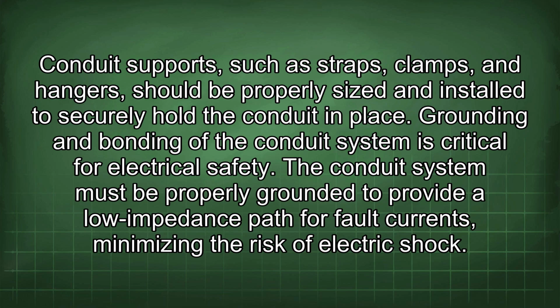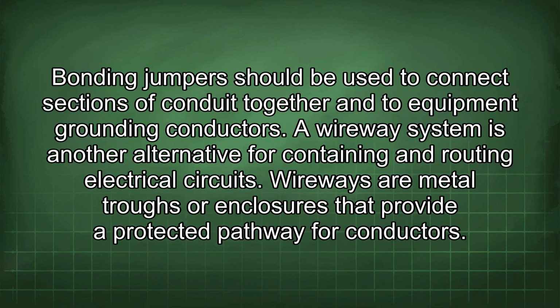Grounding and bonding of the conduit system is critical for electrical safety. The conduit system must be properly grounded to provide a low impedance path for fault currents, minimizing the risk of electric shock. Bonding jumpers should be used to connect sections of conduit together and to equipment grounding conductors.